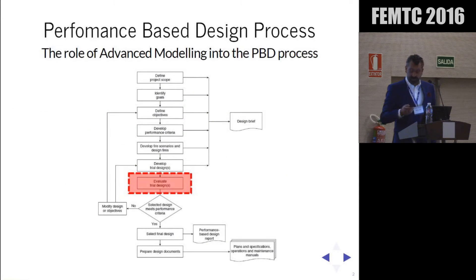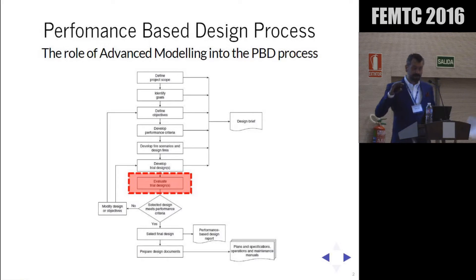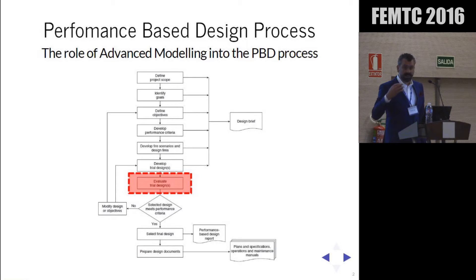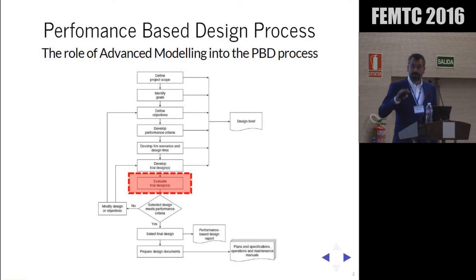What is performance-based design, and where does modeling come into the overall process? This chart comes from the SFPE design guide for performance-based design. Modeling comes in at the evaluation stage. You start by defining a project scope, identifying goals, defining objectives, developing performance criteria, then fire scenarios and design fire, developing a trial design, and then you come to evaluate your trial design — that's where the modeling part comes in.